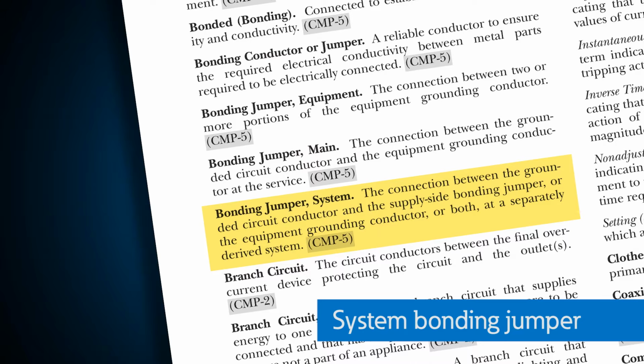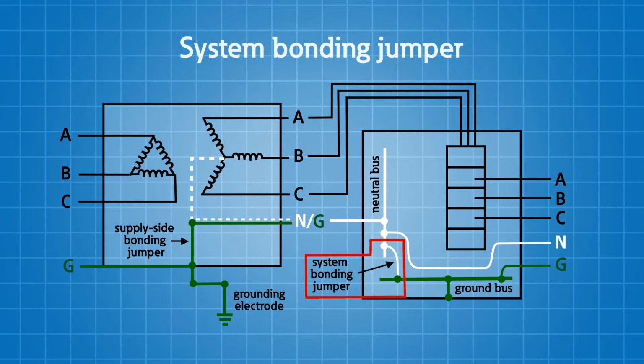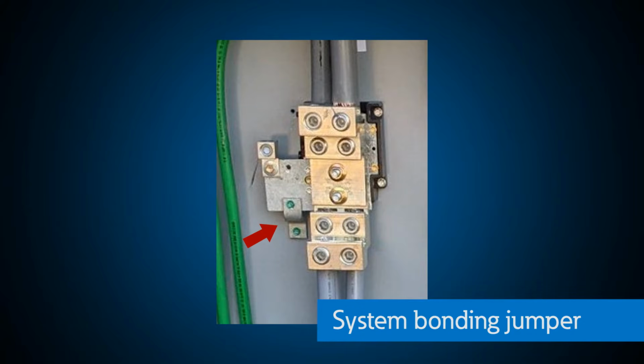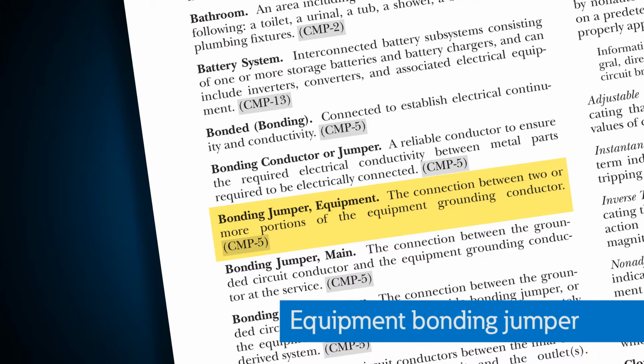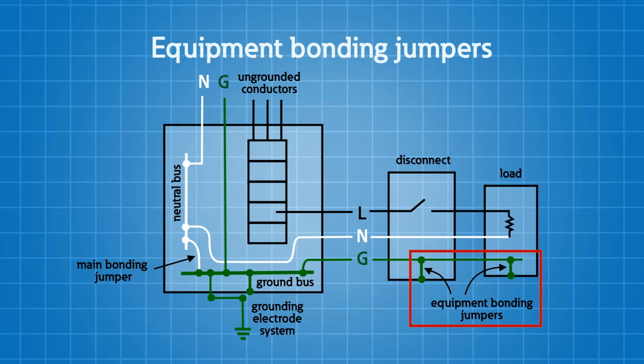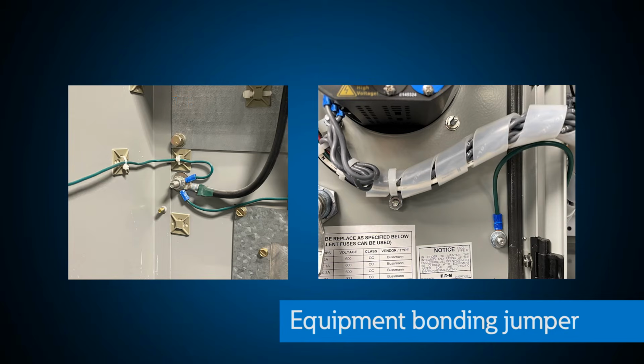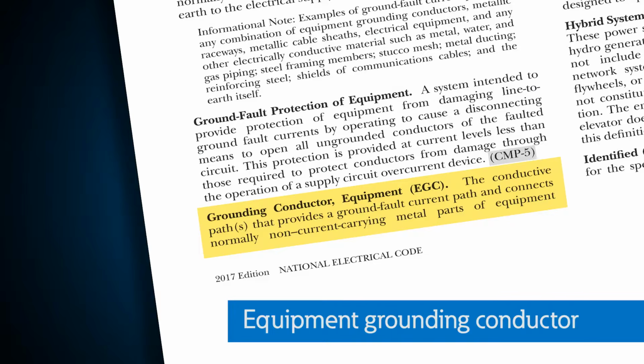All right, so let's talk about the system bonding jumper. This is the connection between the grounded circuit and the supply side bonding jumper. So we have a grounded circuit conductor out there. We have a system ground where we're establishing our ground, and we're going to need to bond those two together, and that's what this is all about. Your equipment bonding jumpers, these are your connections between two or more portions of the equipment grounding conductors. We have to make sure that we bond everything together, and anytime we put jumpers in between your equipment grounding conductor and any of the steel that needs to be bonded, those are your bonding jumpers.